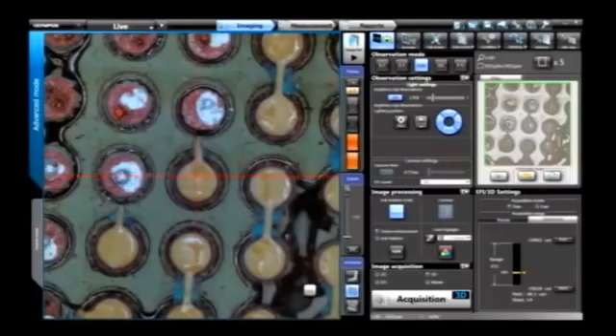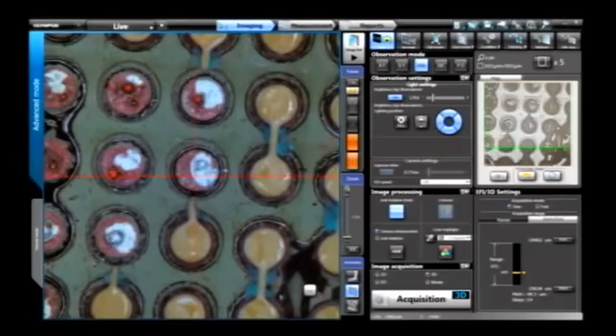Olympus designed a new imaging technique for image processing called WIDER. It's wide dynamic range. This reduces glare and brings up the intensity in the dark areas while still having a very fast refresh rate for the screen movement. And the only downside of this is you don't get quite the surface enhancement as you might get with HDR. Okay. So if you can live without that, this is going to be a much faster way to go. Much faster. Works great for samples that have a high amount of glare that you want to suppress.